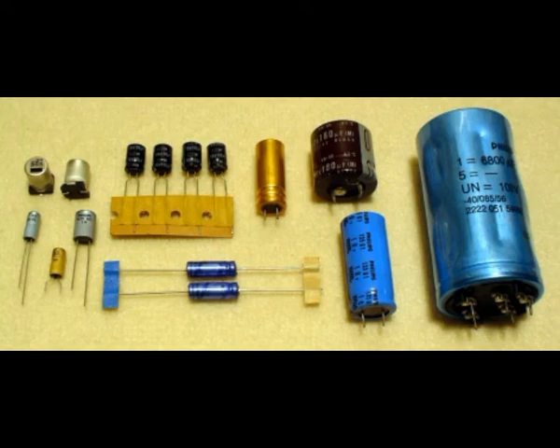Smaller or low-voltage aluminum electrolytic capacitors may be connected in parallel without any safety correction action. Large capacitors, especially large sizes and high-voltage types, should be individually guarded against sudden energy discharge of the whole capacitor bank due to a failed specimen.